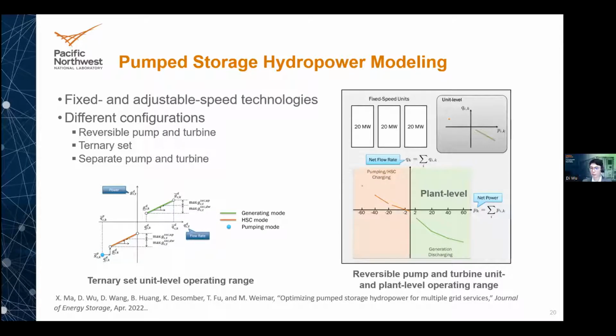We also need to consider different configurations. With reversible pumps and turbines, pumping and generating cannot occur simultaneously at the unit level. With ternary units, we can couple or uncouple the pump from the shaft, providing a flexible operating range through hydraulic short circuit.